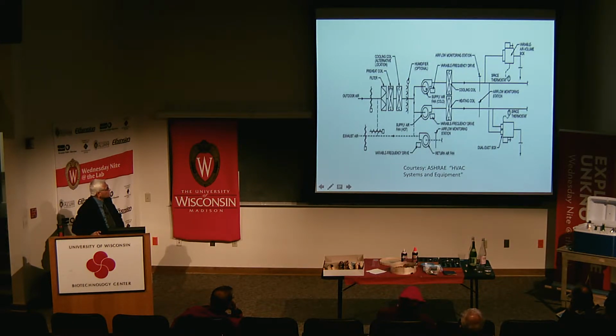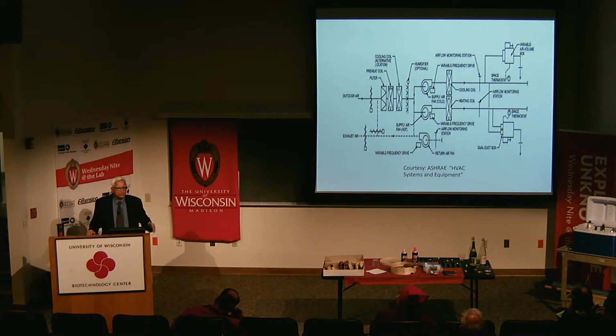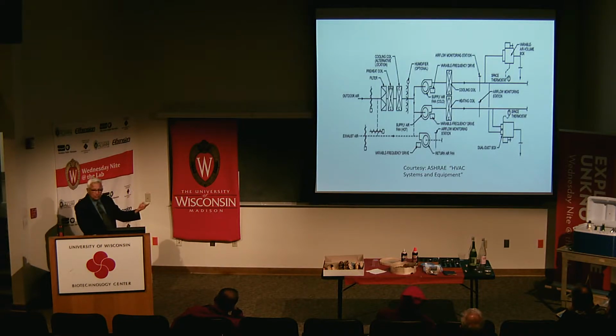this is the supply fan for the cold air, this is for the hot air, and this is the return fan. So the hot air goes here, the cold air goes here, this is the cooling coil, this is the heating coil, and this is the variable air volume box I talked about before, supplying cold air to the interior zones. The reason we use only cold air is that the interior zones are not exposed to perimeter weather, outside weather conditions. Whereas the perimeter zones are exposed to the outside weather conditions.